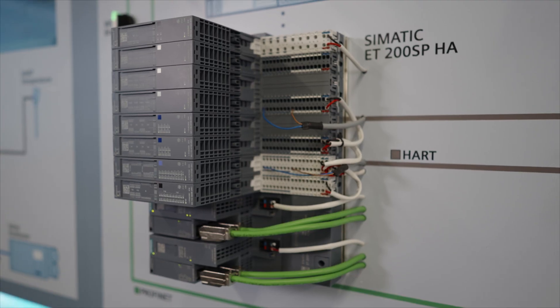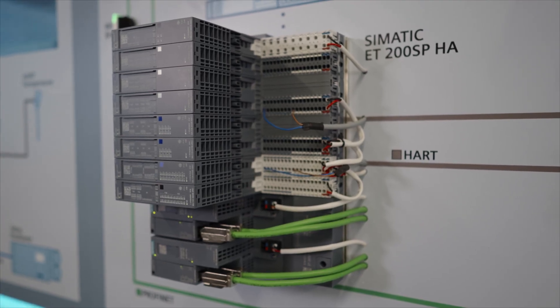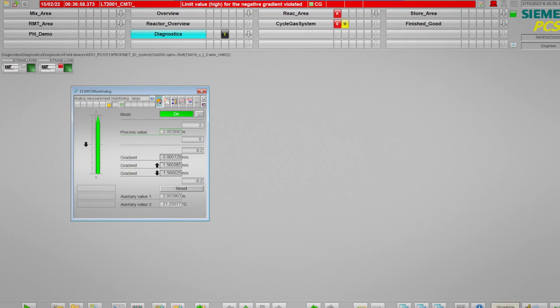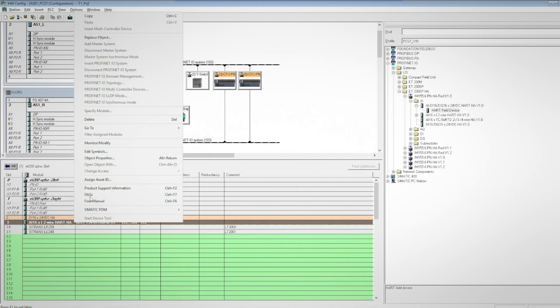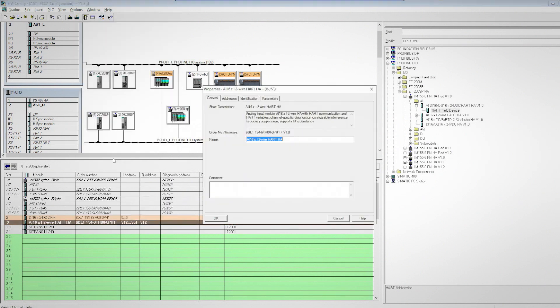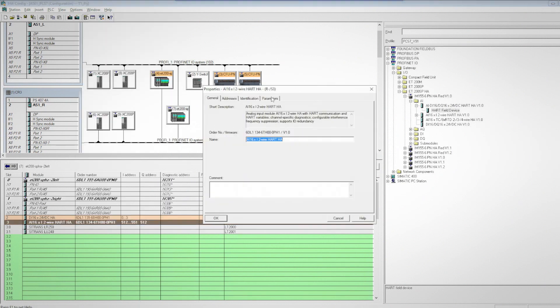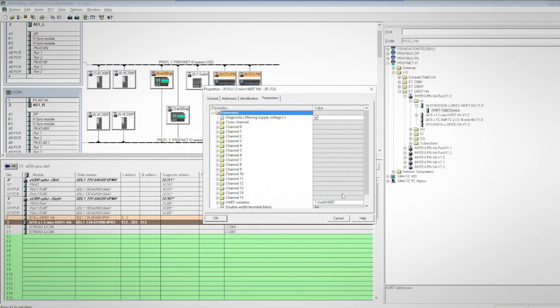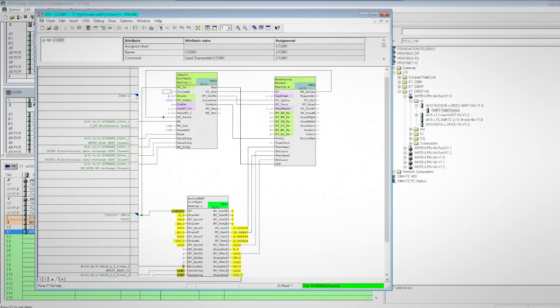HART-capable field devices can be integrated into PCS7 easier and faster than ever with the Simatic ET200SP HA I/O system on PROFINET. HART field devices come with benefits such as device-specific diagnostics, as well as access to additional HART variables through the same analog channel. Up to 4 HART variables can be configured per channel, and up to 64 HART variables per I/O module can be accessed when using the multi-HART configuration and channel block from the PCS7 Advanced Process Library.